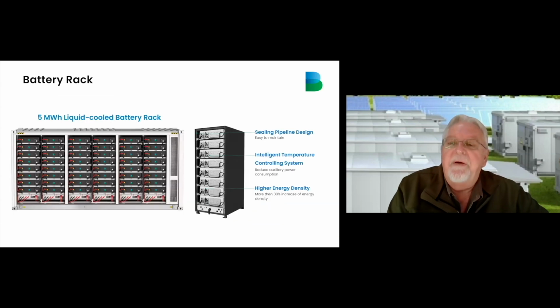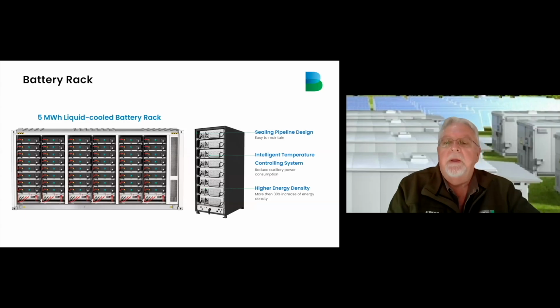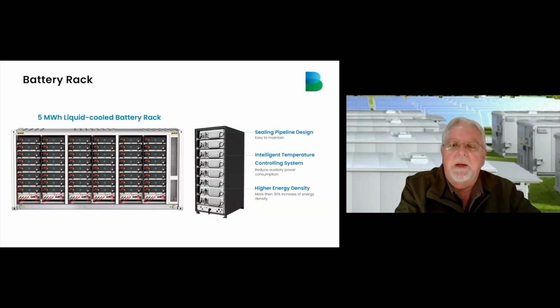Here is an example of a 5 MWh base container configuration with 6 racks consisting of 8 batteries each. Each rack has its own power distribution unit at the bottom. The high voltage battery cables are connected to the PDU, power distribution unit, and the PCS high voltage connectors are connected to the electrical high voltage distribution panel in the electrical room. The PDU also has external AC power supply, communication interfaces, and status and warning lights.